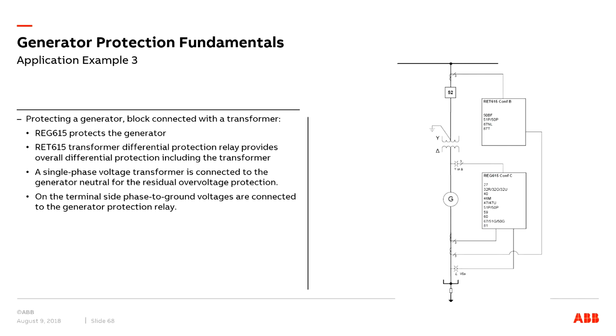This is another example, protecting a generator block or unit connected transformer. We have one relay taking care of the generator protection here, and the other one taking care of the overall protection of the transformer, including the transformers.